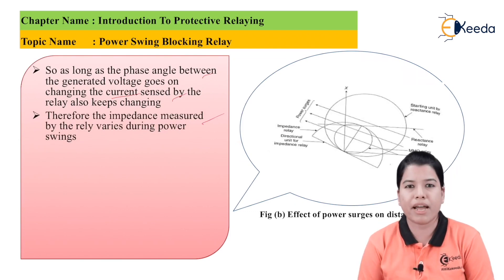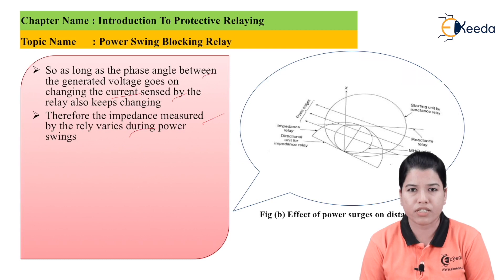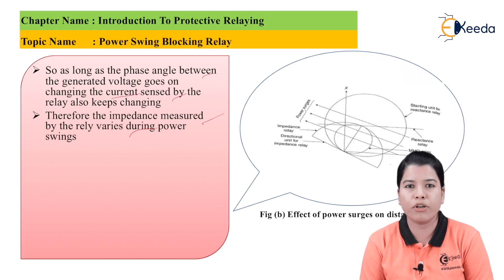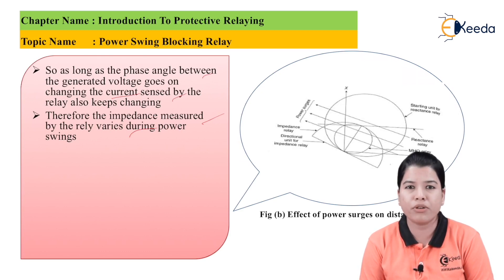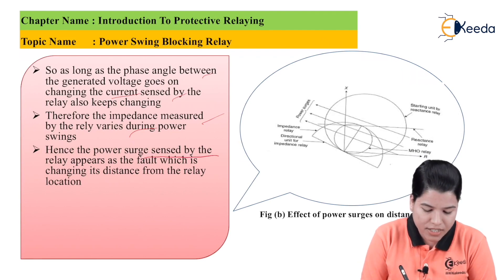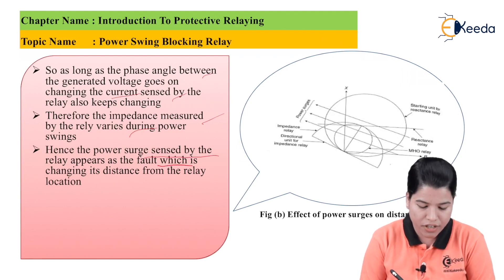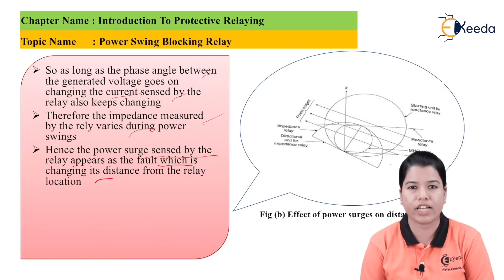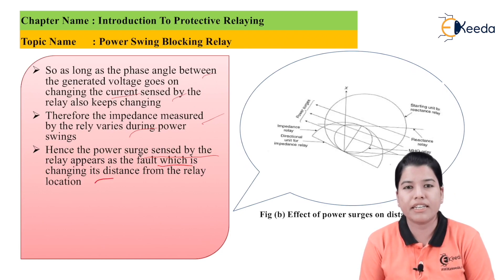Therefore, the impedance measured by the relay will vary during the power swings. In case of a distance relay, it operates when the value of impedance drops below a particular value, so the change in impedance will be continuously sensed. Under continuous power swings, the relay will not be able to decide whether it is a normal or faulty condition. The power surge sensed by the relay appears as a fault which is changing its distance from the relay location.